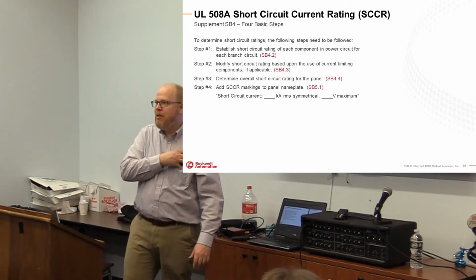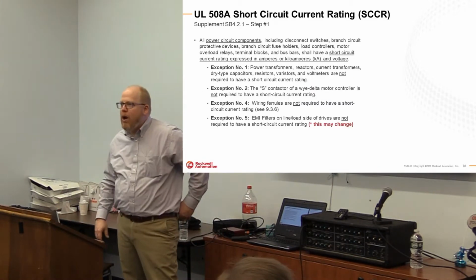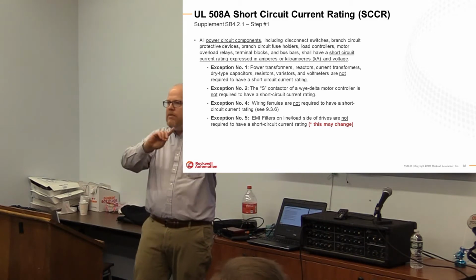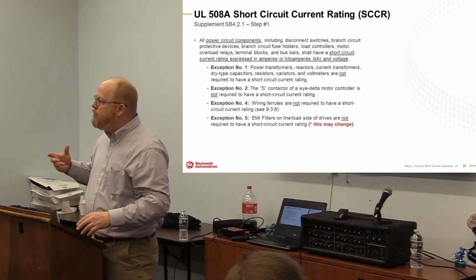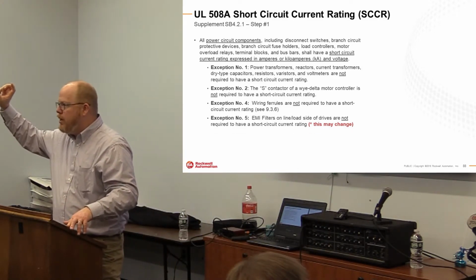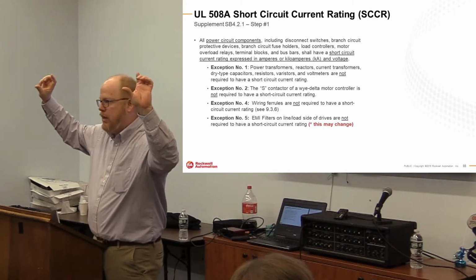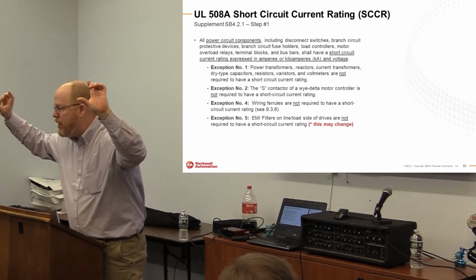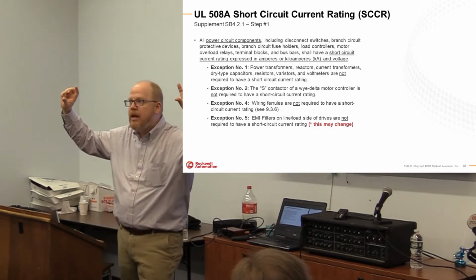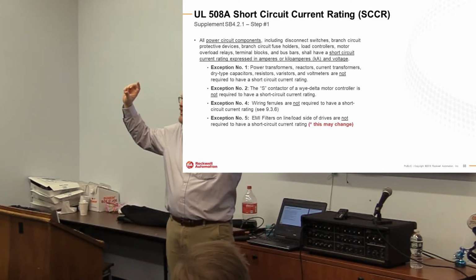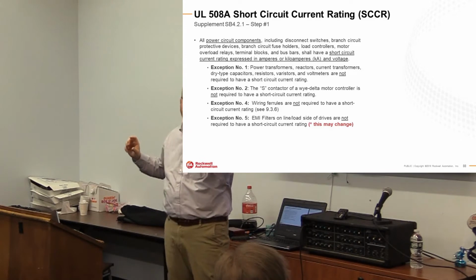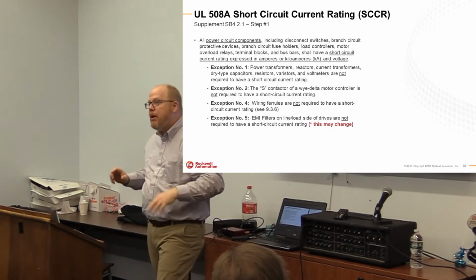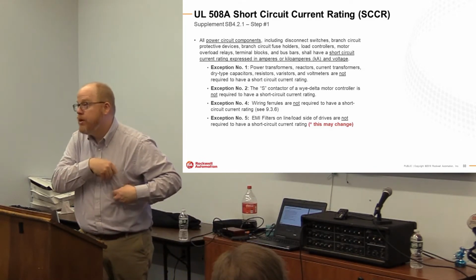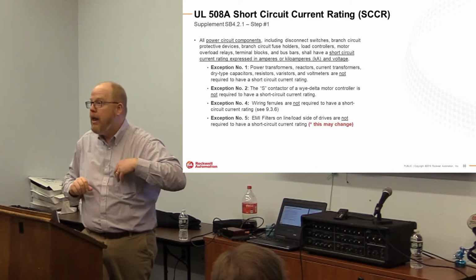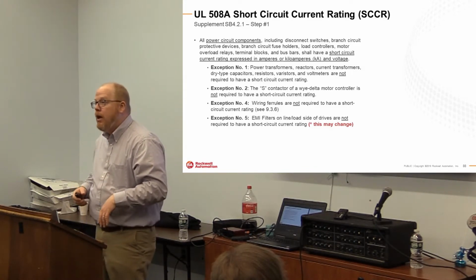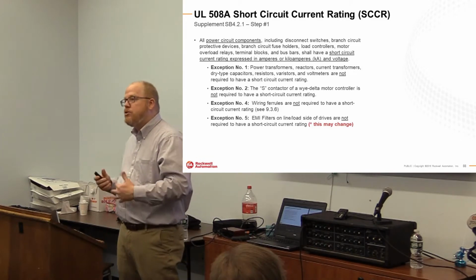So step 1 is talking about all the power circuit components. And why did I underline that? Remember, back at the beginning of the UL combo, I had said you need to be very clear what a control circuit is versus a power circuit. And it all depends on the load that you're attaching to it. So if you attach motors, it now becomes a power circuit and becomes susceptible to the requirement of SB. And that's what you don't want to do. But here's the deal. All the power components, including disconnects, shall have a short circuit current rating in kA and voltage. That's really what it's saying.